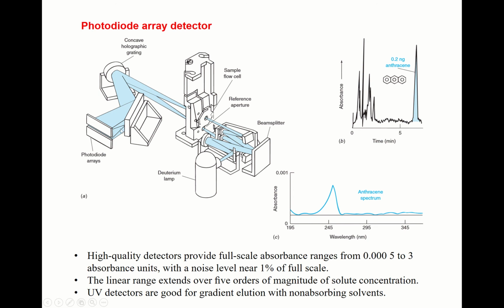That's the characteristic of photodiode array detectors. The noise level is near 1%. Quite good. The linear range extends over 5 orders of magnitude of solute concentration.